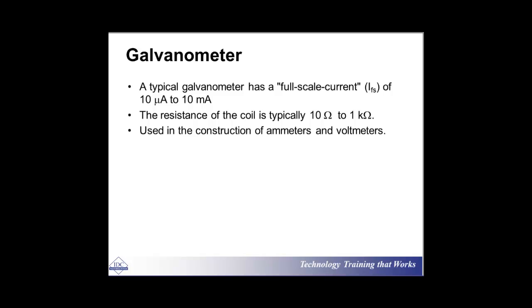For example, you can set your ammeter, if you have used this galvanometer as an ammeter, to read something between 10 microamp to 10 milliamp, or between 10 milliamp to 100 milliamp, or between 100 milliamp to something, and so on. So you have got a selector key. When you change the selector key, you are changing the number of turns of that coil. As a result, the magnetic field will change, the torque will change, and the force applied to that needle will change.